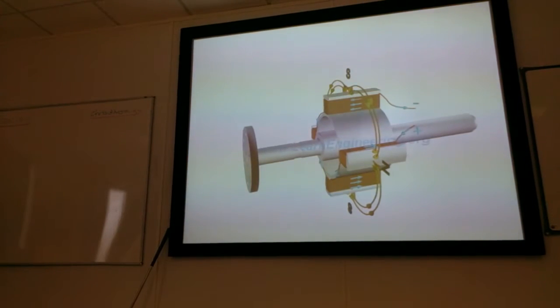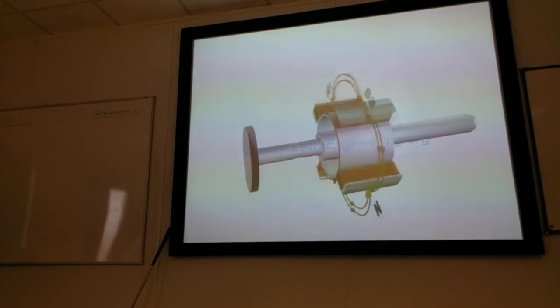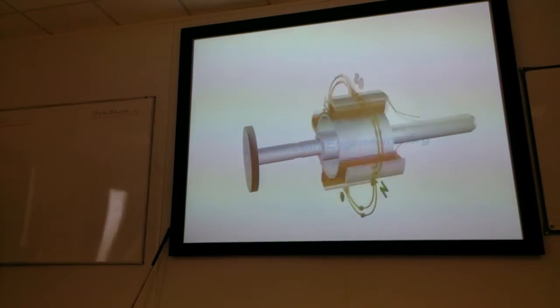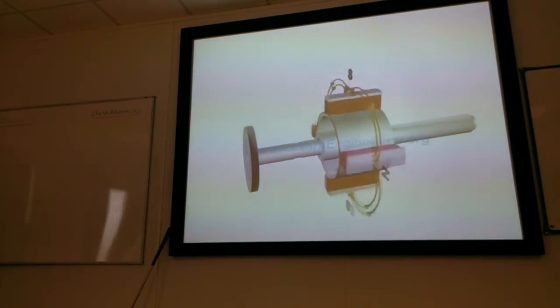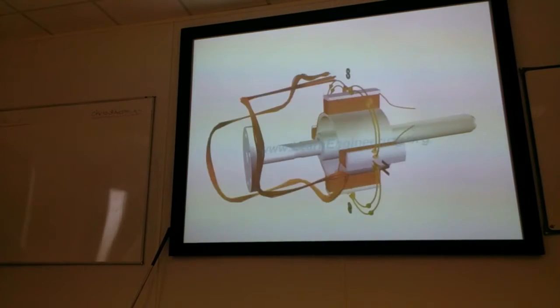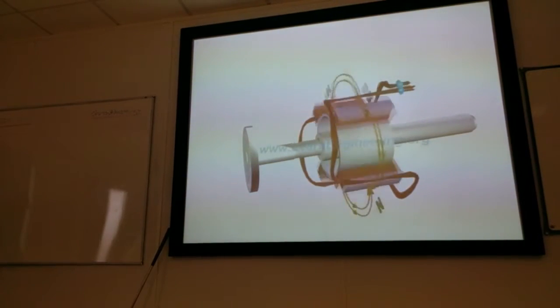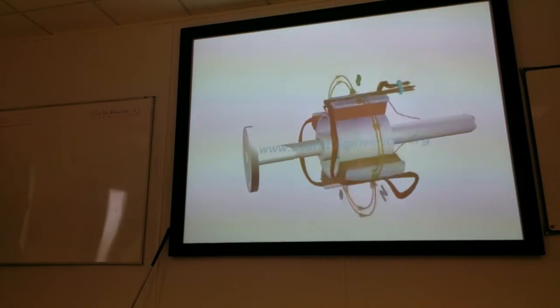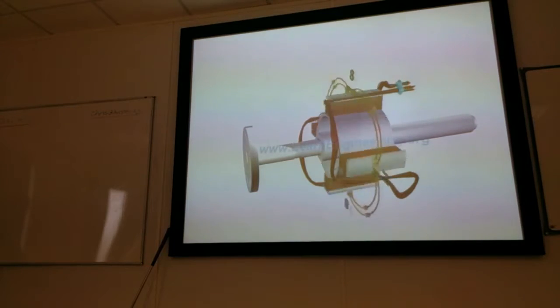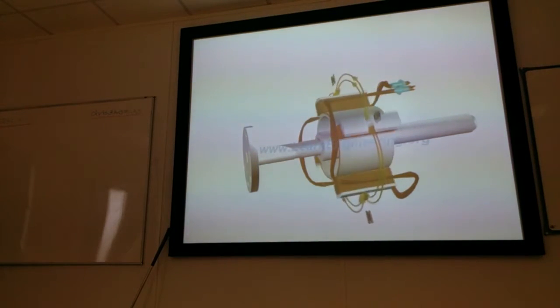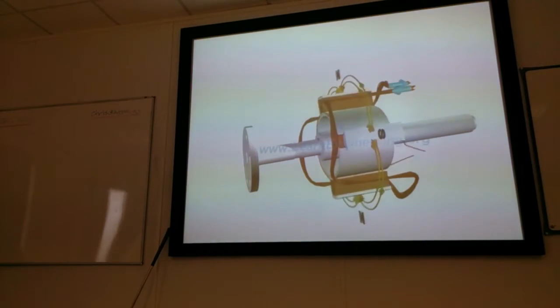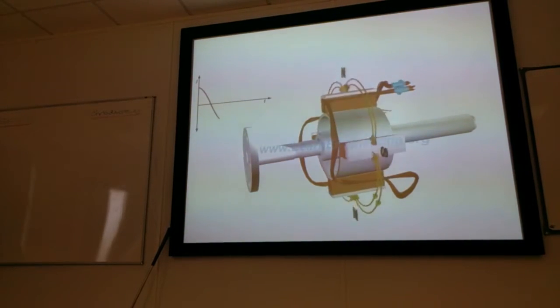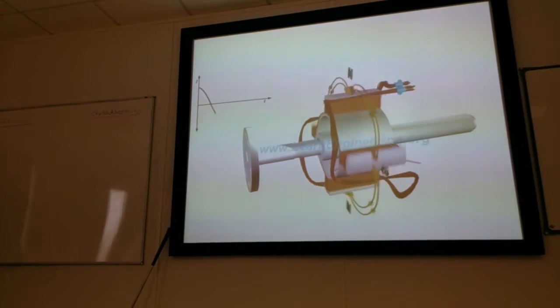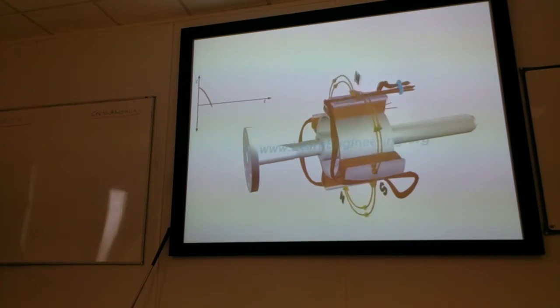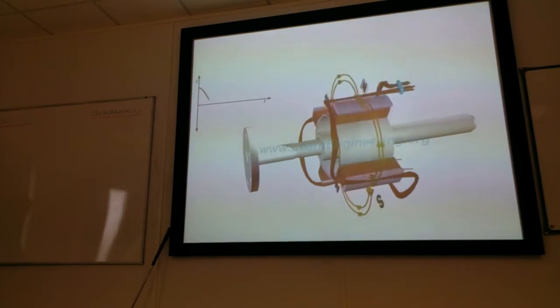The rotor is made to rotate by a prime mover. This makes the rotor flux also rotate along with it at the same speed. Such revolving magnetic flux now intersects armature coils, which is fitted around the rotor. This will generate an alternating EMF across the windings. Here is a slowed-down version of rotor-stator interaction. For this 4-pole system, when the rotor turns half revolution, induced EMF takes one complete cycle.